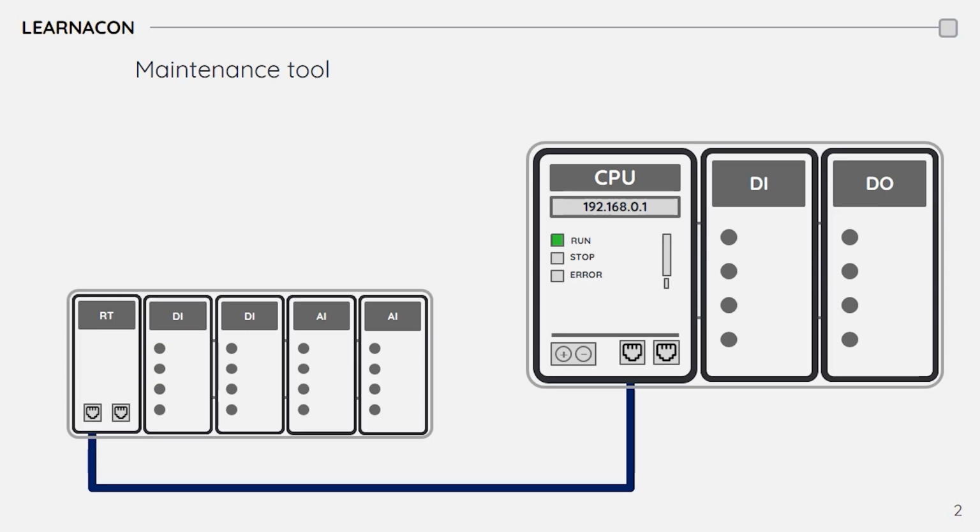Keeping the system operational is a key part of PLC maintenance. There are a number of scenarios that can cause the PLC to fail and go to stop mode. For example, if the CPU loses communication with remote I/O, it may enter into stop mode. After fixing the issue, you can restart the PLC to activate the process from the beginning.